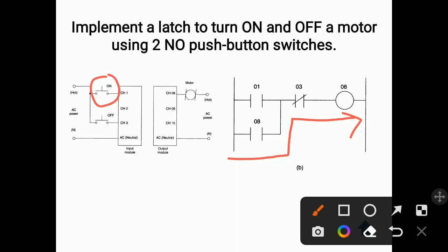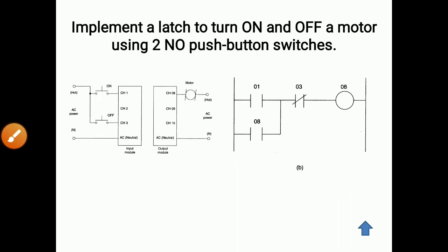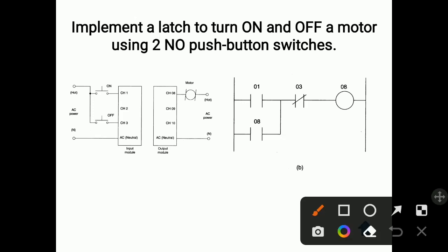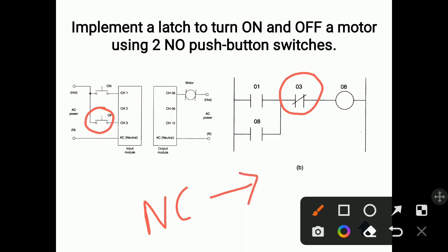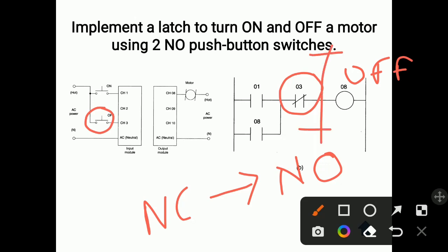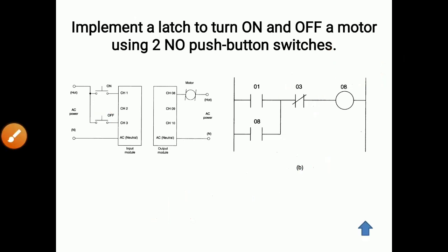Now suppose the motor is continuously on and you want to turn it off — in an emergency situation. We have used one OFF switch here: switch number three, which is normally closed. By pressing that switch, you can turn the motor off. When you press switch number three, it gets open — the normally closed contact becomes normally open — and the motor turns off because the supply gets cut from that position.